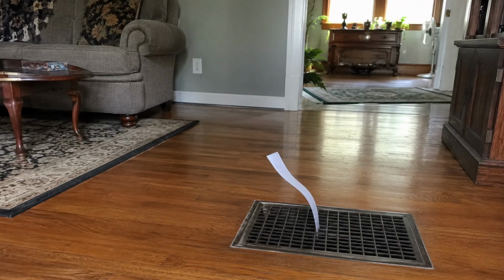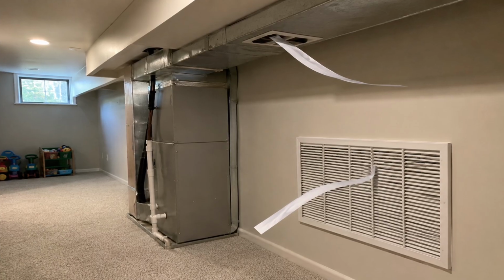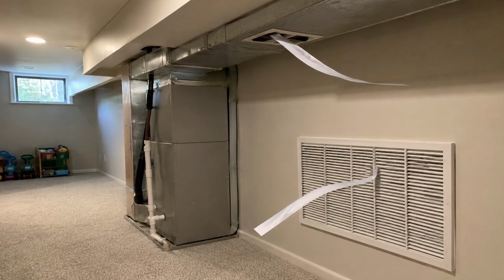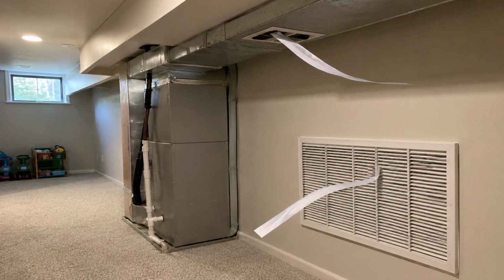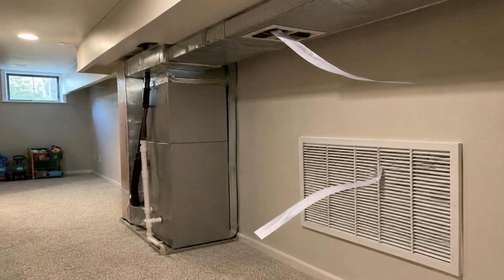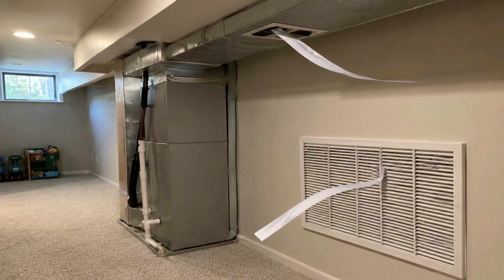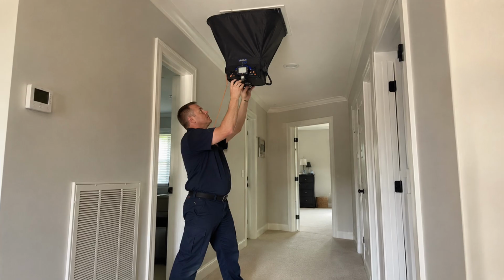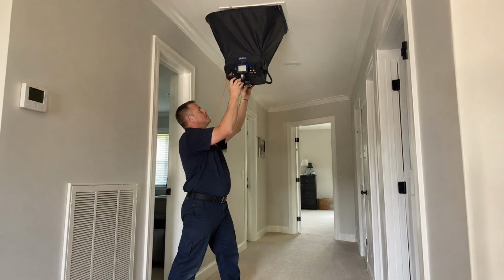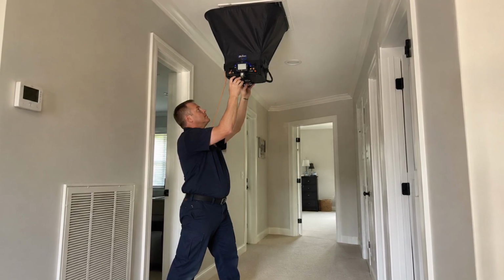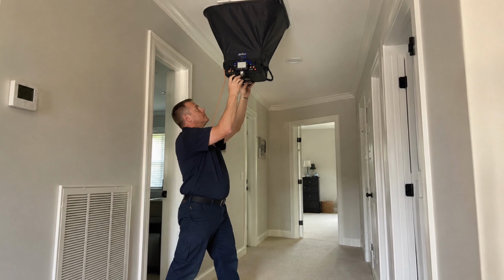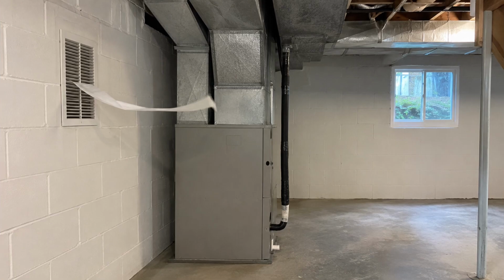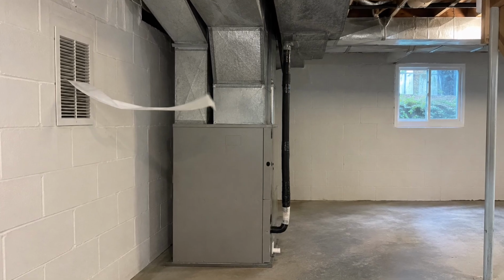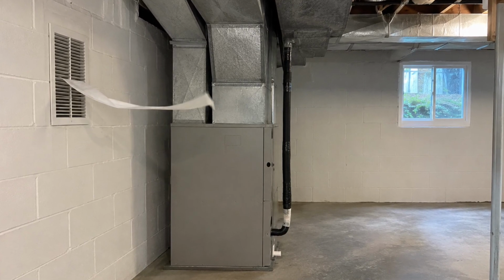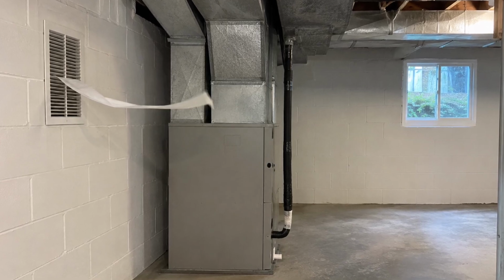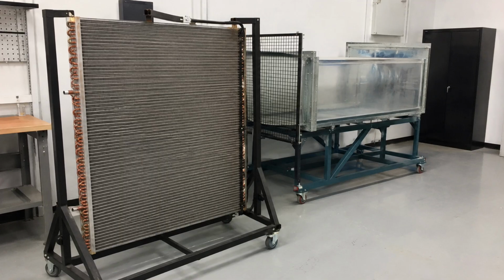The first is the blower itself. With many older blowers, airflow falls as the duct resistance rises. Some newer constant airflow motors try to compensate by increasing speed and power until they reach their limit. So I will not tell you that every blower uses more electricity each time one register moves. The exact response depends on the motor and its controls. What I can tell you is this. Extra restriction pushes the system away from the airflow it was set up to deliver. That can mean less airflow, more blower effort, more noise, or some combination of the 3. It is not free.